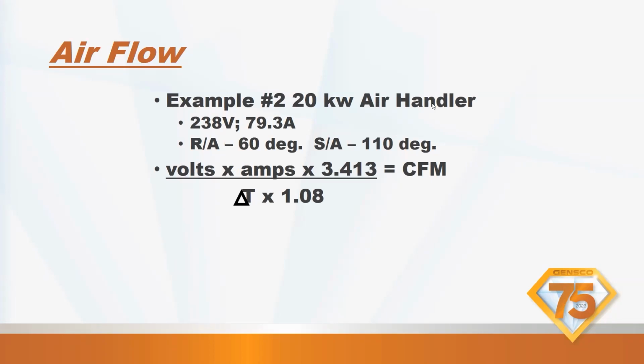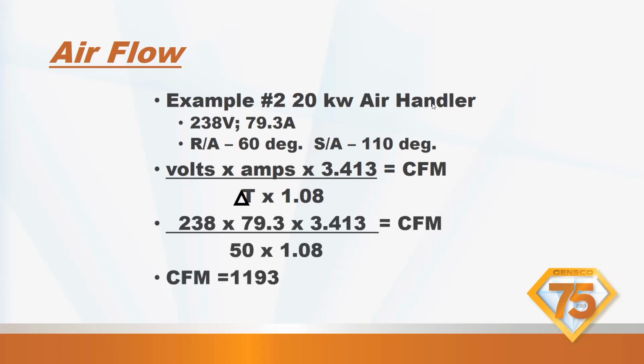This is an example for a 20 kilowatt air handler. So we've got 238 volts and 79.3 amps. We can assume that this is either a single point connector or we've already added up our amp draws on our separate breakers. Okay. Our return air is 60 degrees. Our supply air is 110. We're going to do the calculation: volts times amps times 3.413 divided by the delta T. Delta T is temperature rise, supply minus return, times 1.08. There's our math. There's our delta T. And there's how many CFMs. These are very easy to do on site without any special tools. All you need is a thermometer and a calculator. Okay.